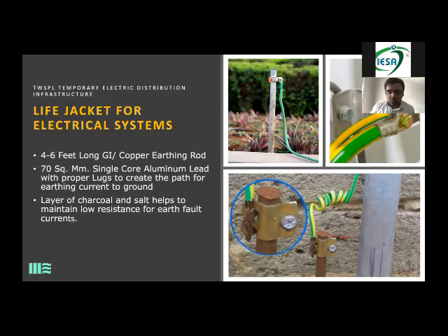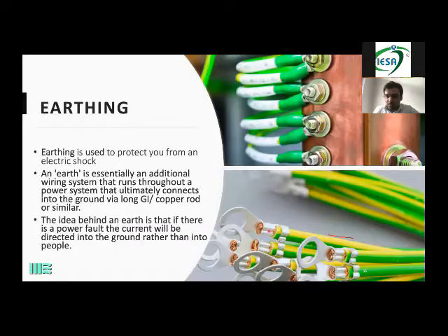So normally what we do is dig these GI or maybe copper rods inside the ground. These rods could be from 4 feet to 6 feet. 6 feet is definitely suitable. So 6 feet rods go inside the ground. Over here you see that this green color wire is connected to this rod with a lug. So this is a lug, if somebody doesn't know, what we also call a thimble. So these wires need to be thimbled.